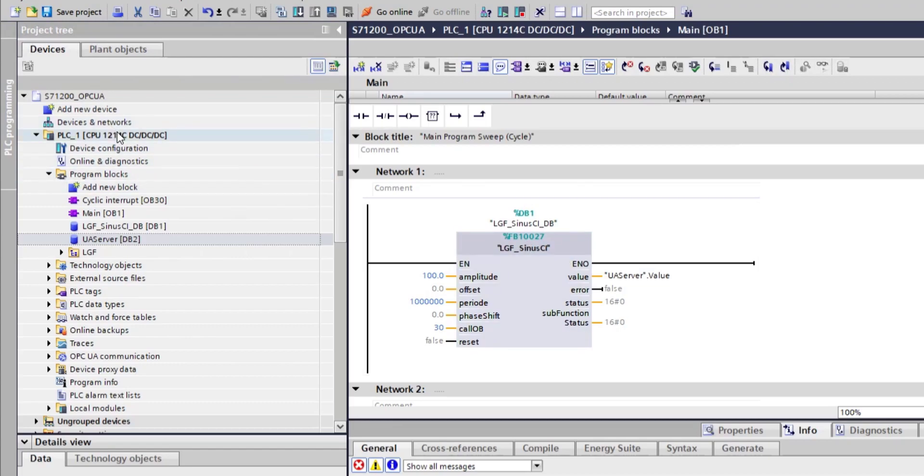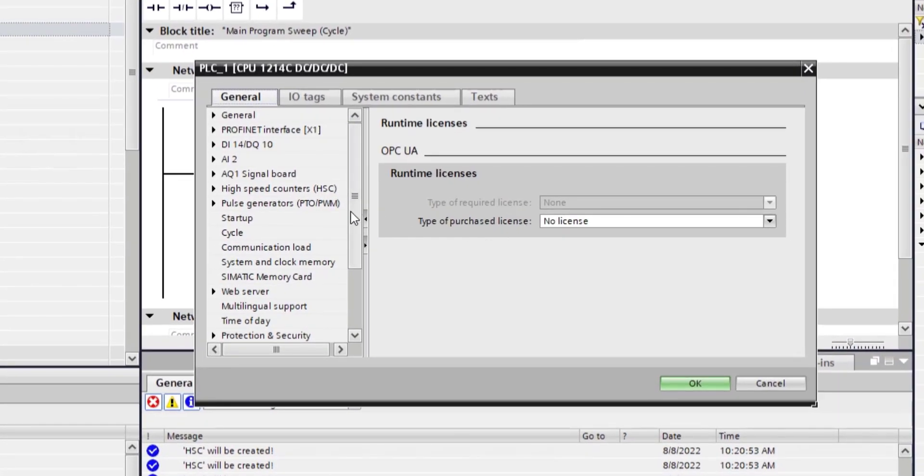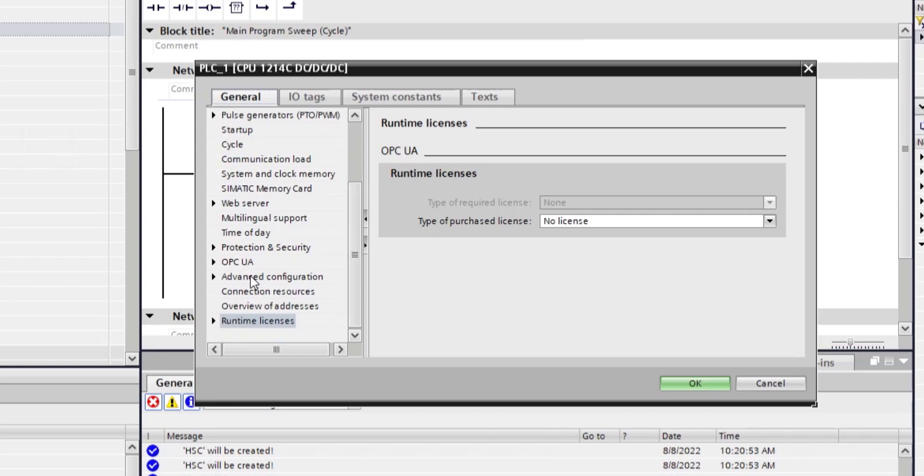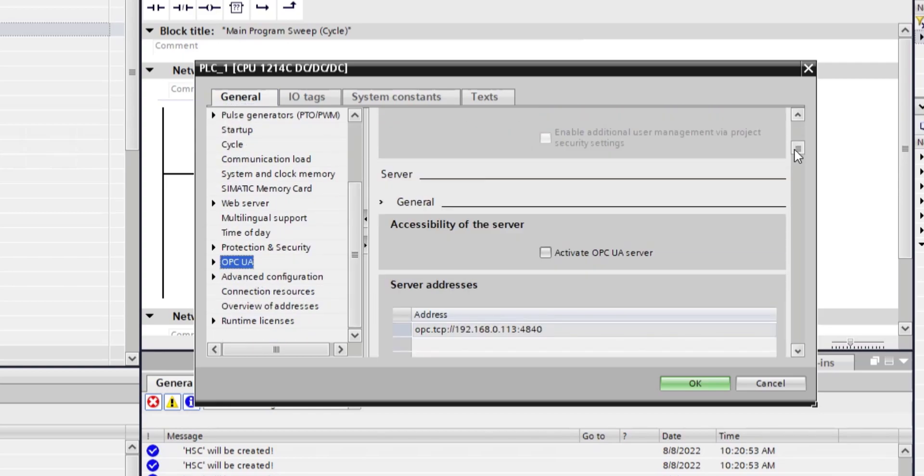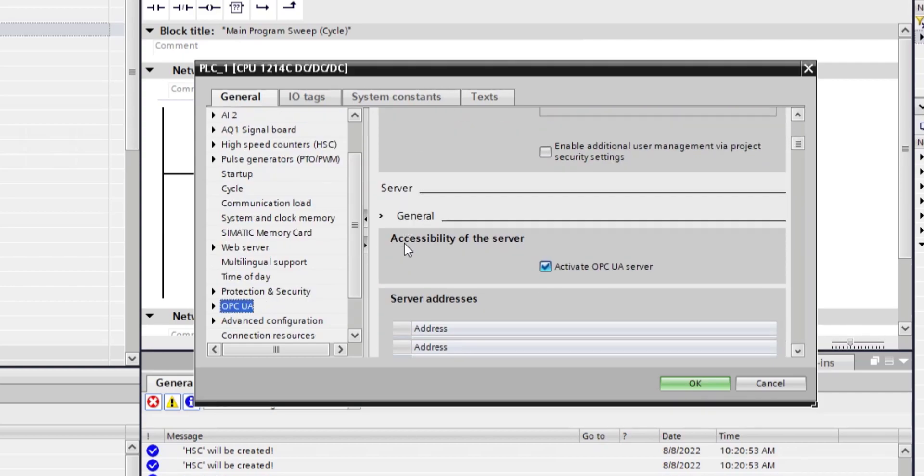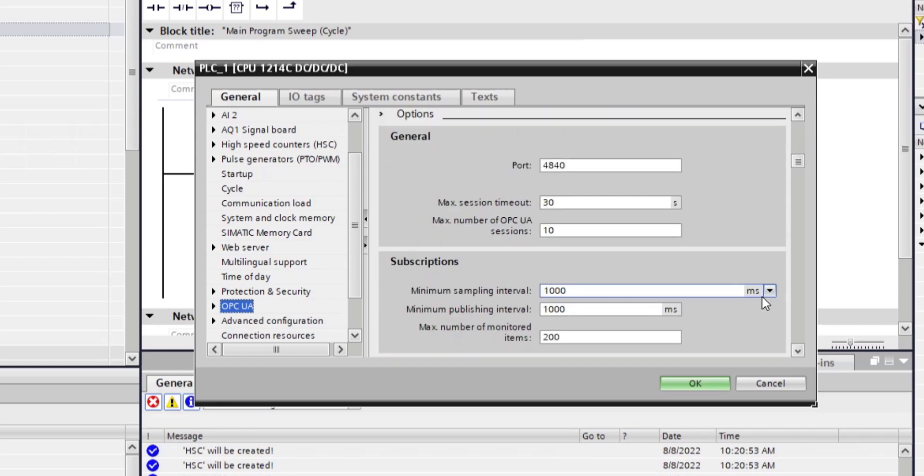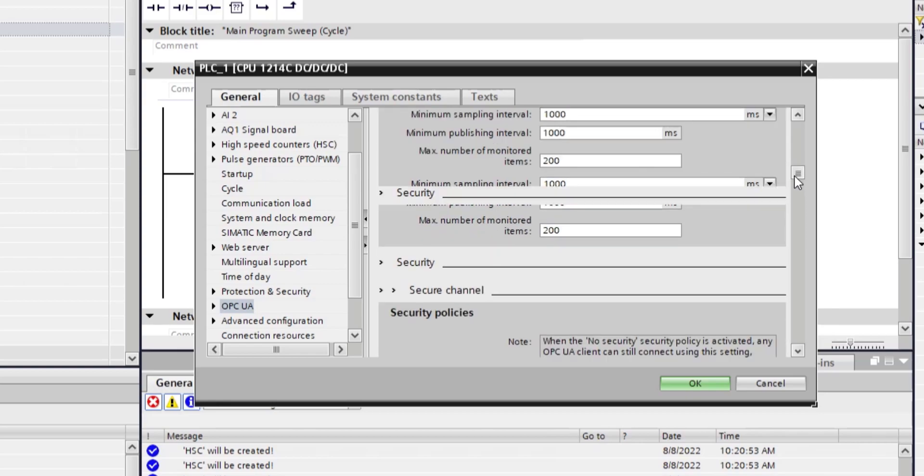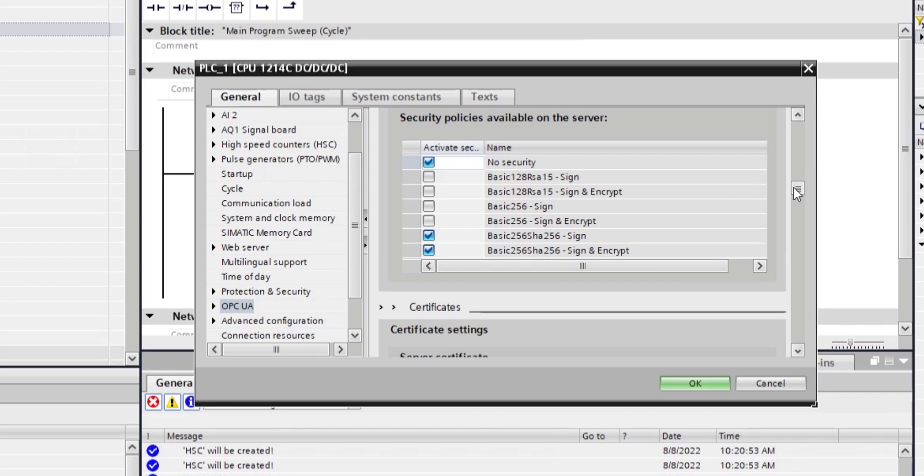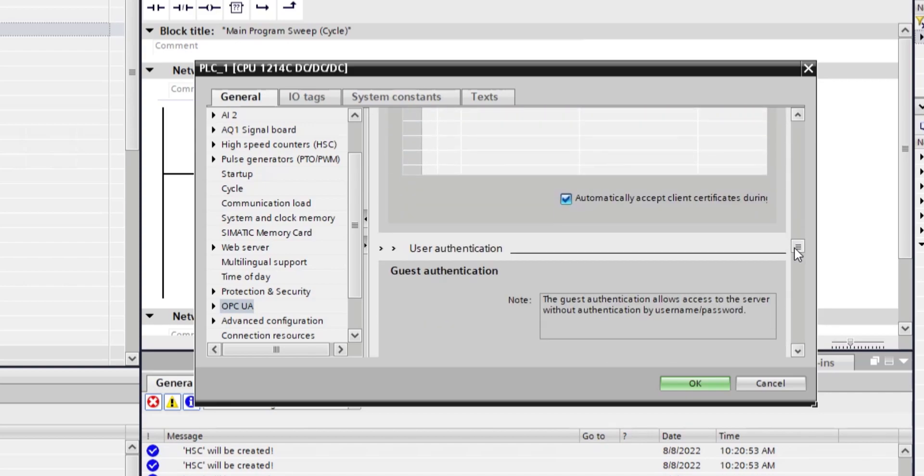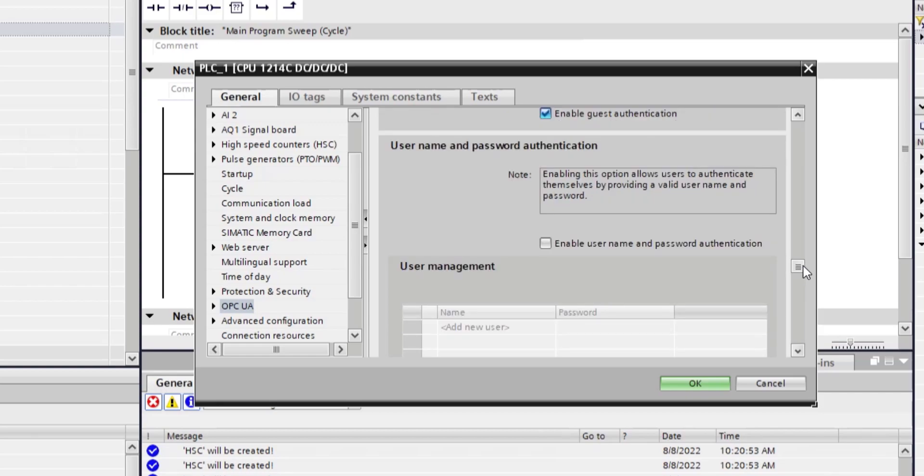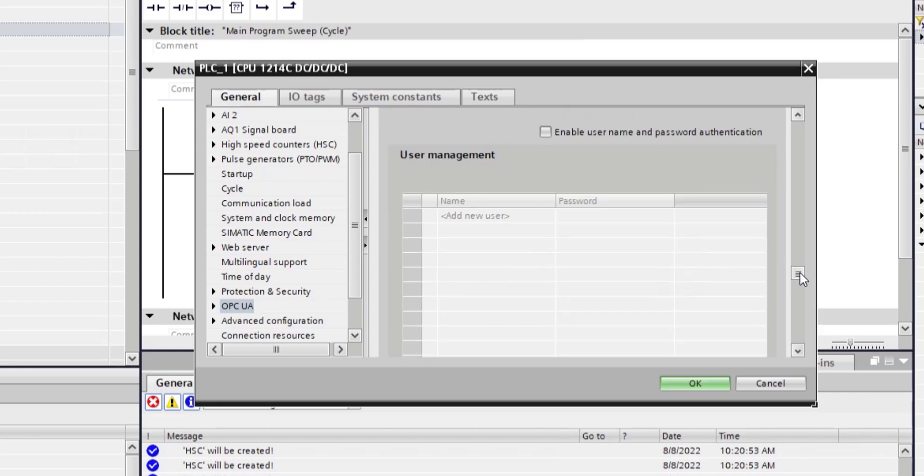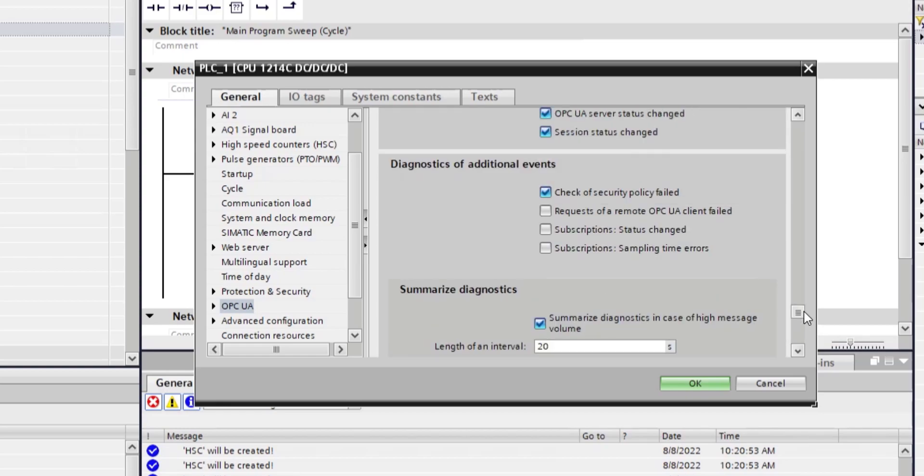So now if I go to the properties of my S7-1200 and go to OPC UA settings, here I can activate the OPC UA server. The default parameters will enable this with the guest access on port 4840. So this is the default port with these basic security policies. So there will be no protection. Again, it's not something that I'd recommend. I would recommend that you create a user with a password, use certificates for encryption, but just here to quickly show you how you set it up, we can leave it at this.